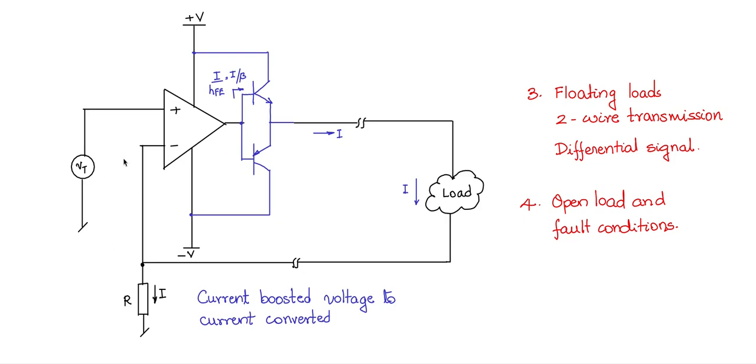So between that you have the range 4 to 20 milliamps current will flow. If current is 0, then the one and only condition that can happen is something has gone bad. Because Vt, when it goes to 0, 4 milliamps, the voltage, an offset voltage, zero span circuit should come in, which will dictate an offset voltage where 4 milliamps will flow when Vt is equal to 0. I will show that in a moment.